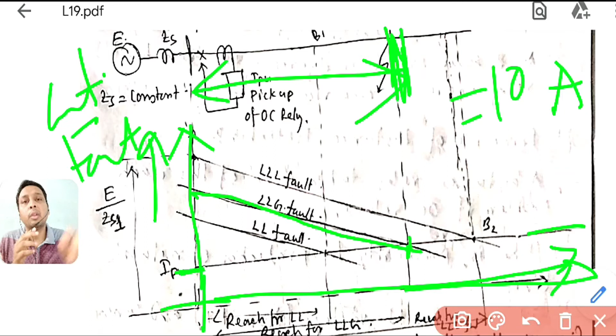Now what will happen for a less severe fault, an LL fault? For an LL fault to give this 10 ampere current, the fault should occur nearer, because an LL fault is less severe and gives less current. So if an LL fault occurs farther away, it will not give you 10 ampere. Suppose here there is an LL fault, it will give 10 ampere. So you can see for an LL fault, your 10 ampere is coming here only. The relay can sense up to this much only, so your reach becomes A to B1 now. If an LL fault happens beyond that, your current will be less than 10 and the relay will not detect it.